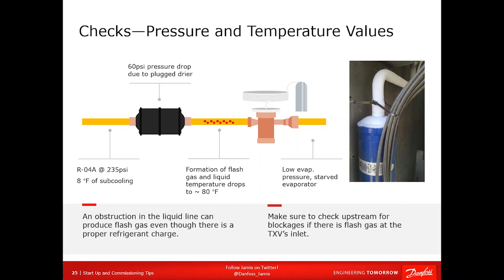So how do you catch this? Well, before you condemn anything, especially before you add refrigerant, if you've got a TXV that's hunting, before you condemn that TXV, look upstream. Take it from me. This has happened to me before. All right, you could have a stuck solenoid valve. You could have a ball valve that somebody didn't open up properly. You could have a filter dryer that's got a huge pressure drop across it. This is easily done under your first observations. It's pretty easy to catch this stuff, right? It may not make frost, but you could see sweating, and your hands will tell you a temperature difference.